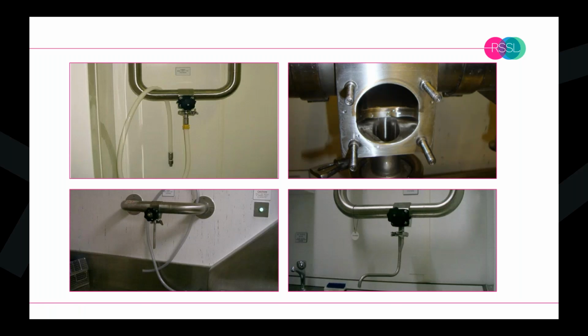Of some poorly maintained hosing. So we've got hosing that's not disconnected in the top diagram. When tubing isn't in use, it should be disconnected so it's free-draining, and the tubing should be changed at regular intervals with freshly sanitized tubing. We've also got again tubing that's not free draining properly. We've also got a picture there of an inappropriate valve that holds water. So that's a huge source of contamination. And then we have an example of a dead leg. Where we have the dead leg, again, we've got a great opportunity for a biofilm to develop.